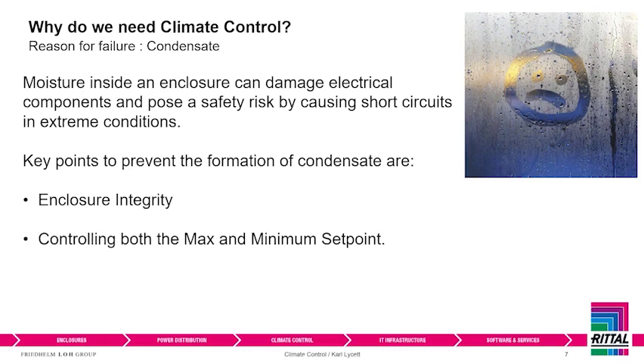So you need to be installing adequate heating in there, enclosure heaters, to make sure that the floor as well as the ceiling temperature inside your enclosure is maintained within a nice limit, because otherwise that fluctuation up and down and up and down is going to cause condensation to form, and if left unchecked, can be dangerous.